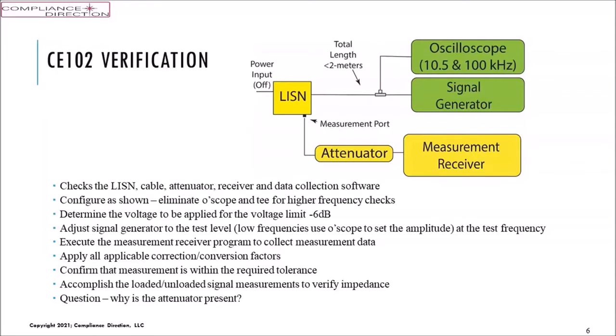And why do we put that attenuator there anyway? The LISN attenuates power frequencies. Well, when we first start up and apply a high voltage like 120 volts, 240 volts, etc., there's an inrush of current through the LISN coupling capacitor that gets terminated by the measurement receiver. That high level of current, because of the short circuit action of the capacitor, damages the receiver. So we put the attenuator in to prevent that overload.